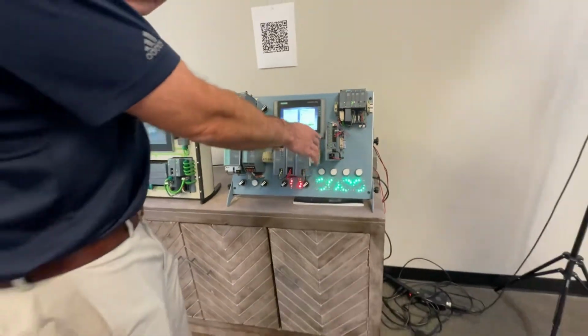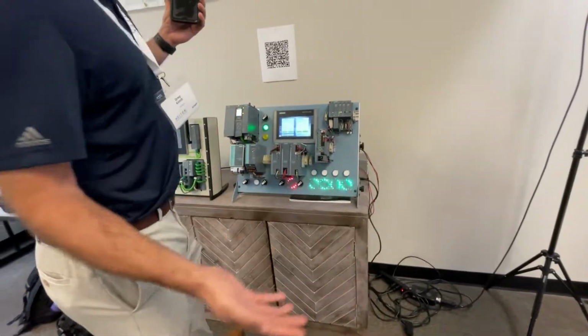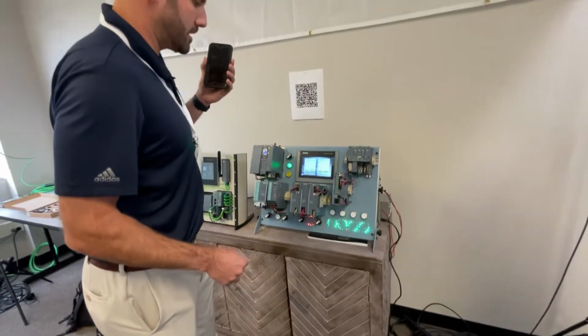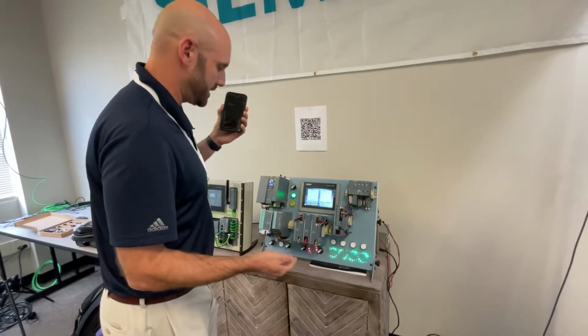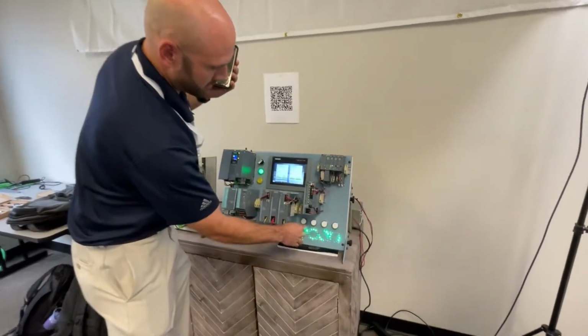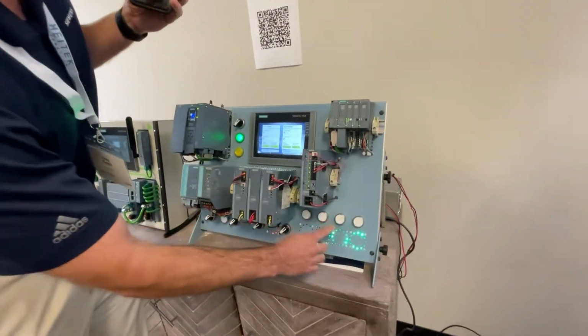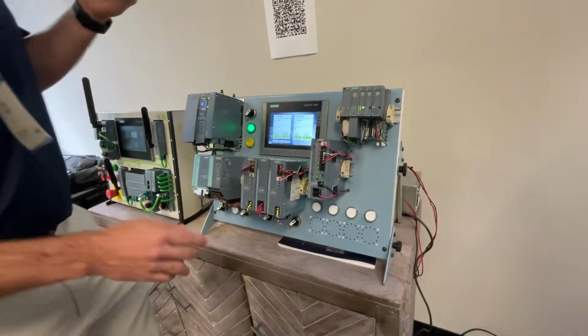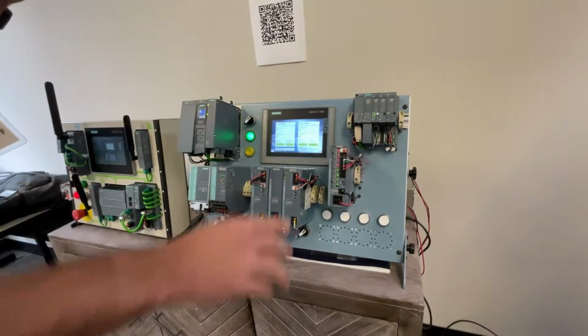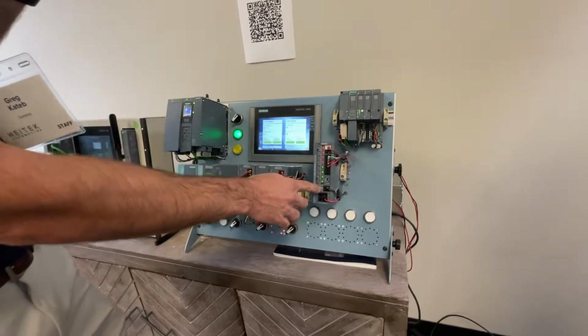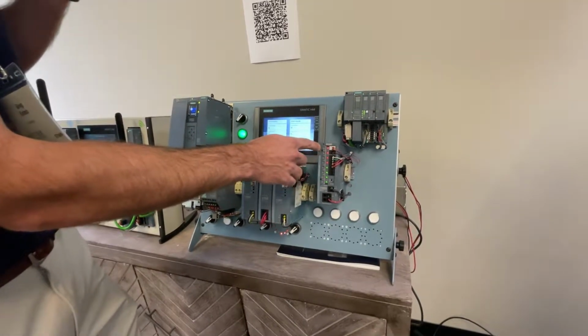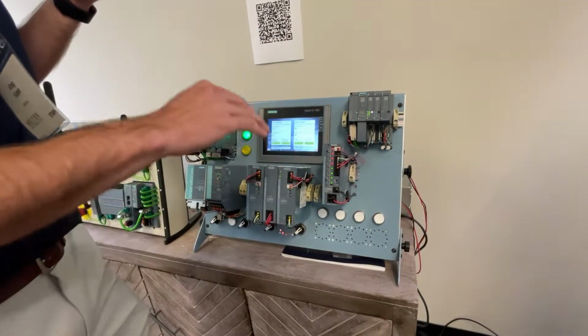As far as the selectivity module goes, this is an alternative to circuit breakers for your electronic fault protection for 24 volt DC power. So this is just to simulate some short circuits. You'll notice that instantly they all turn off and there's no impact between the different channels. So we have 8 output channels available, and each one of these is adjustable between 2 to 10 amps. So basically when that current exceeds that threshold, it'll instantly turn off.